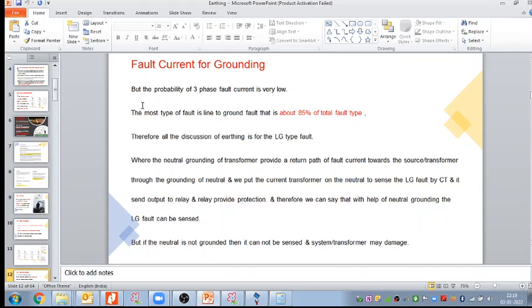Fault current for grounding. The probability of a three-phase fault current is very low, as we discussed in the beginning. The most common type of fault is the line to ground fault, about 85% of total fault types. Therefore, all the discussion of earthing is for the line to ground fault type. The neutral or grounding transformer provides the return path for the fault current towards the source or transformer through the grounding of the neutral. We put the CT on the neutral to sense the line to ground fault, and it sends output to the relay, and the relay provides protection. Therefore, with the help of neutral grounding, the line to ground fault can be sensed.